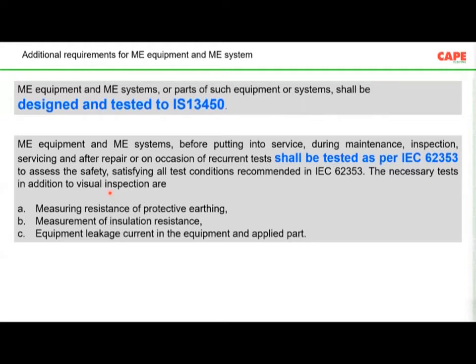Now, for the last 2 slides, I was showing the requirements of the medical IT system. That means the OT panel, which you generally call, is one of the safety measures. But the additional safety measure is the ME and ME system. Medical equipment and medical equipment systems shall be designed and tested as per IS 13450. This is a new standard. It is, of course, from the IEC standard.